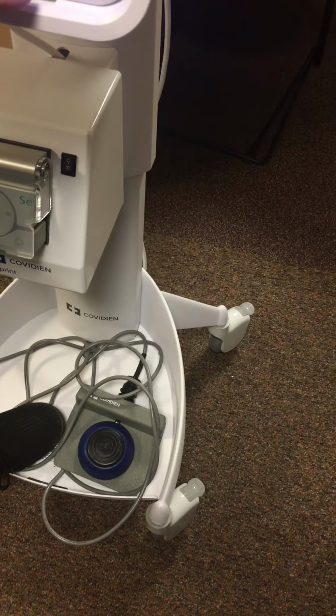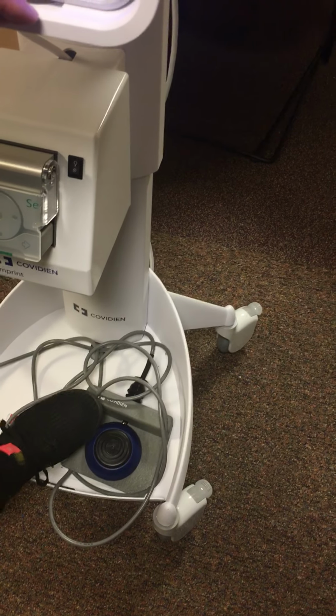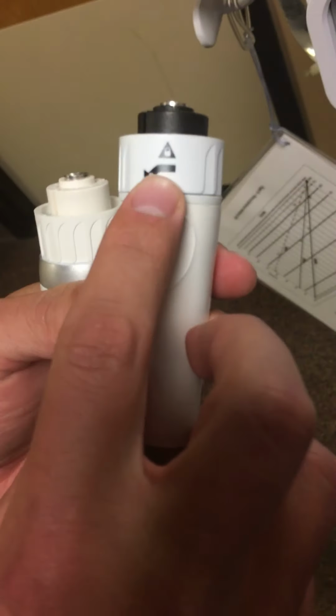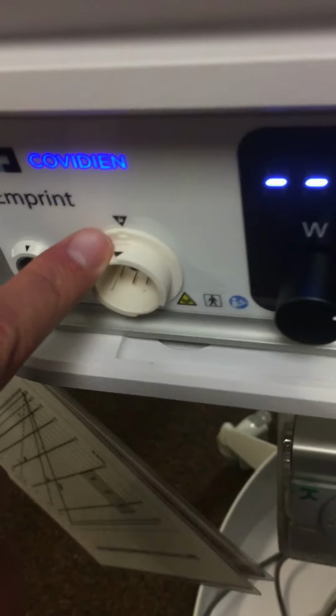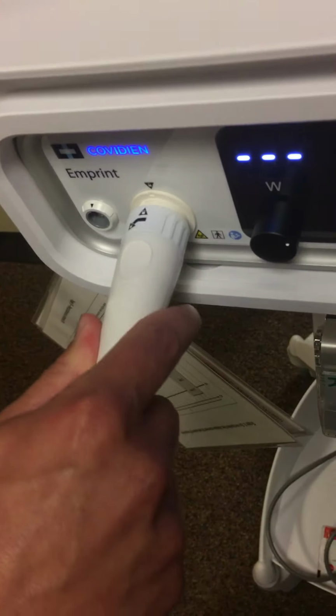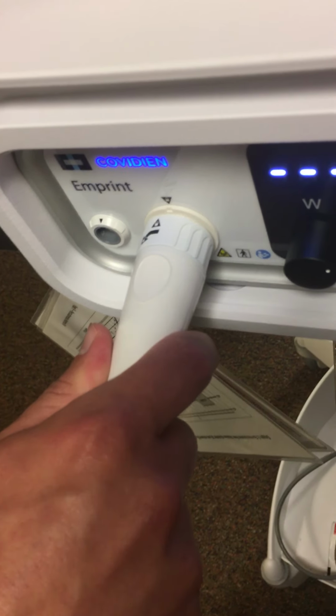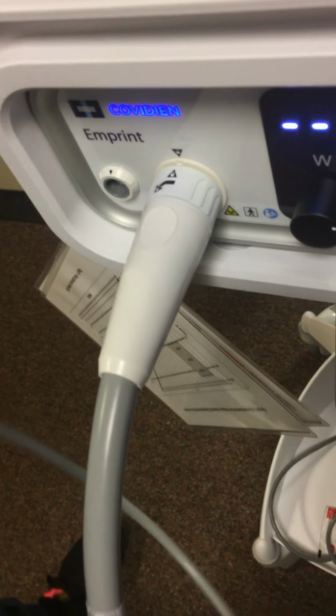Also, if we look down here at the foot switch, the physician can also control the start and stop of the ablations by clicking once on the foot switch and once again to stop it. Okay, so I'm going to go ahead and plug this in. Looking at the high efficiency cable here, we see a black triangle. You see a black triangle on here. A common thing that happens is people try to plug in the blue, but always remember to match the colors. So black to black, we're going to just gently line these up, press gently, and it's going to click just like that.